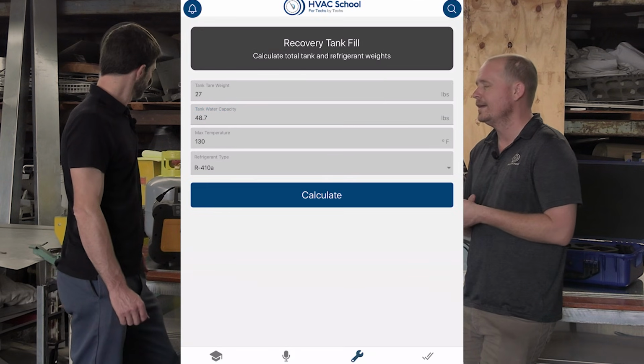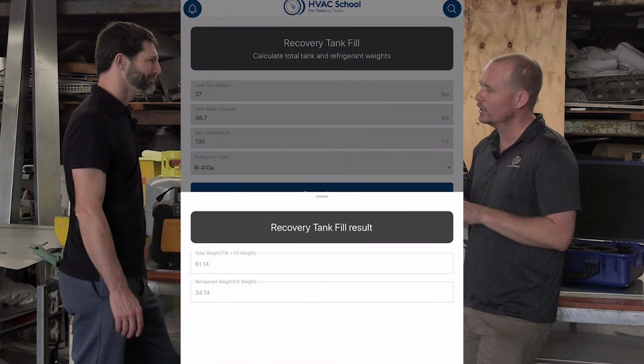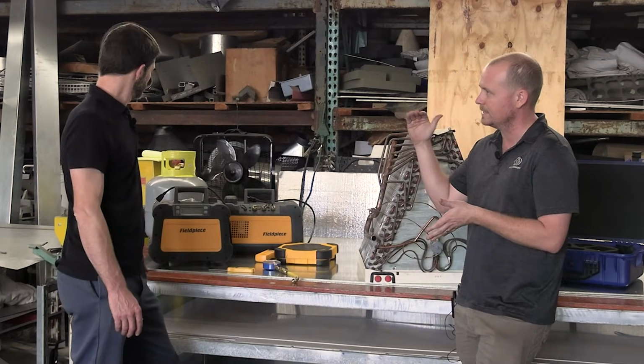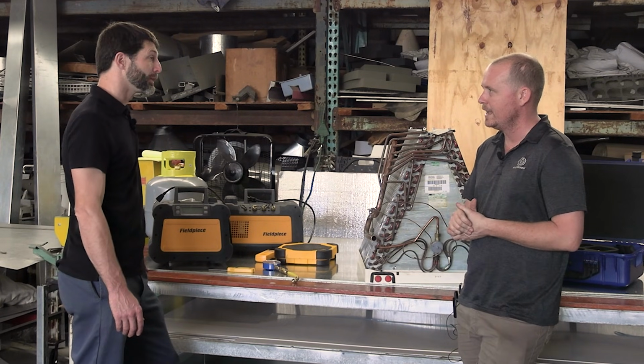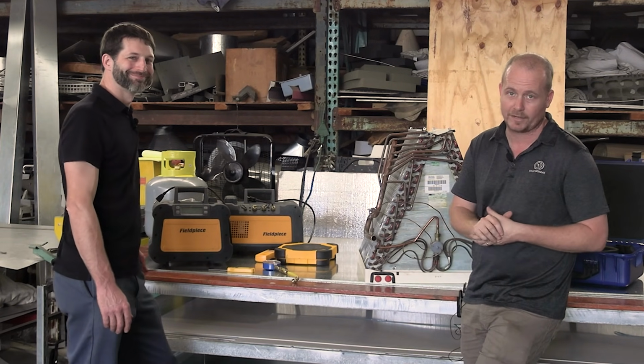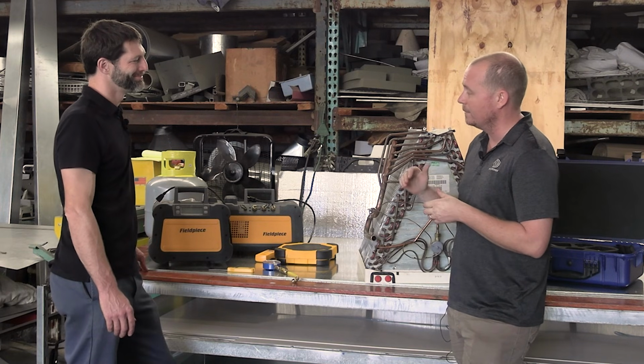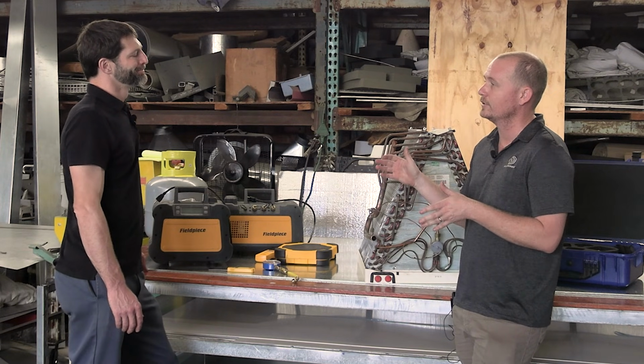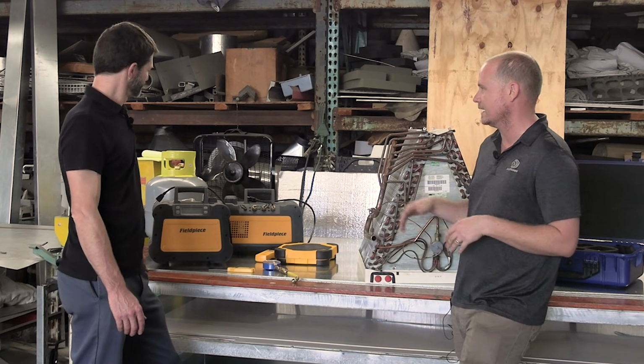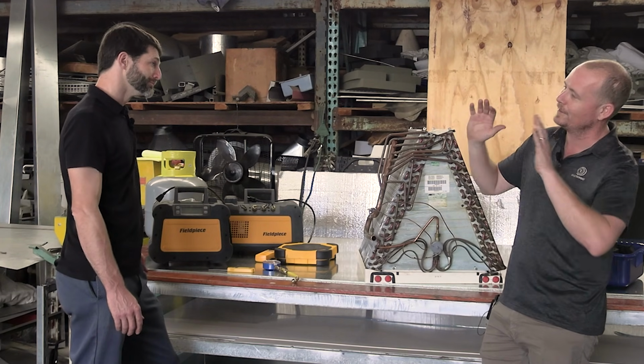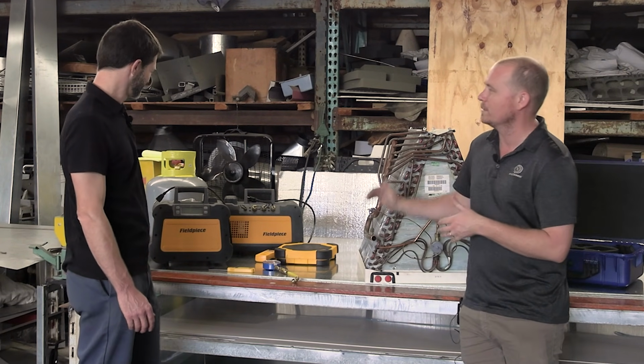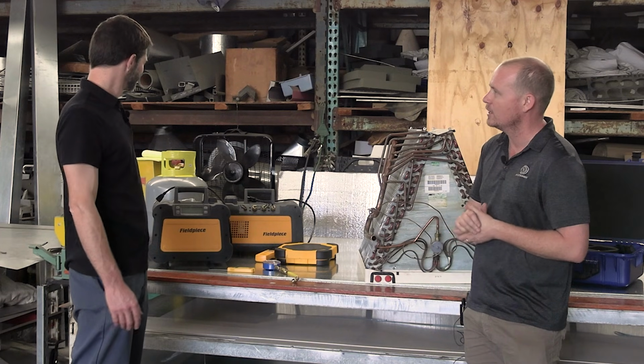And generally speaking, it's kind of an accepted trade practice that we use 130 degrees as sort of the maximum temperature. That's sort of the worst case scenario in the back of your van, at least hopefully, if you're not working in Death Valley or something like that. Even though the AHRI standards talk about 77 degrees kind of being the test standard. But again, without getting too horribly nerdy with this, we just want to make sure we don't fill the tank more than 80%. That's no bueno.